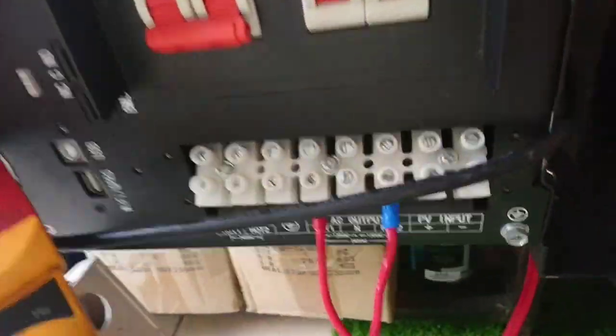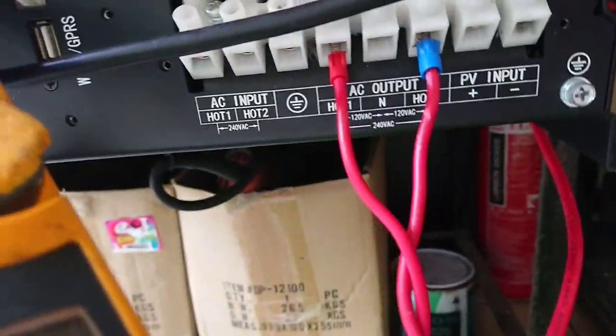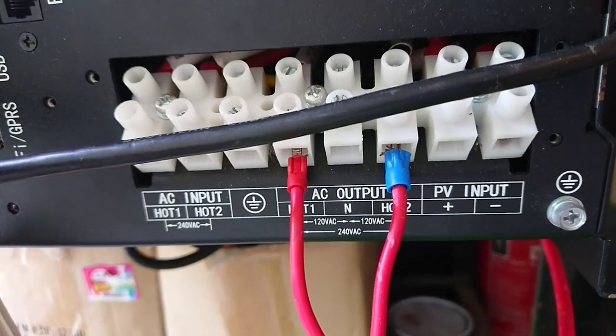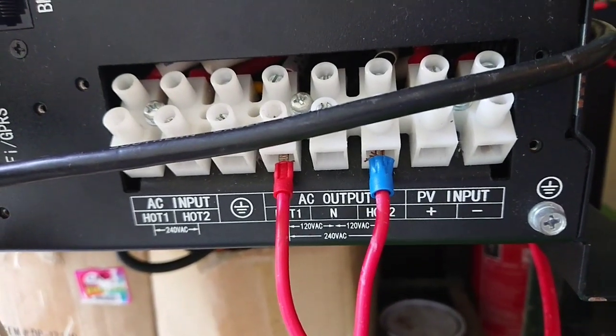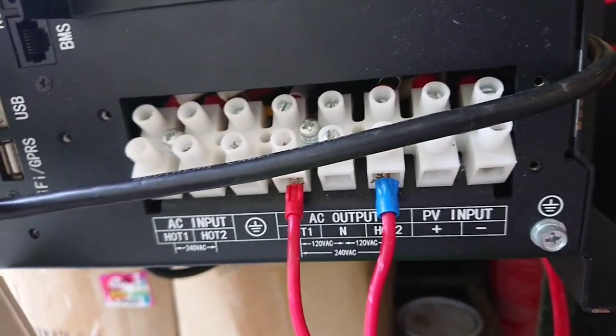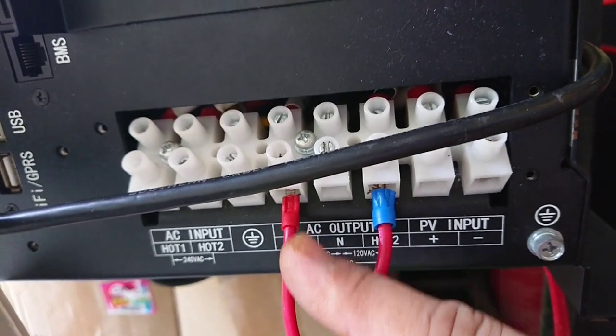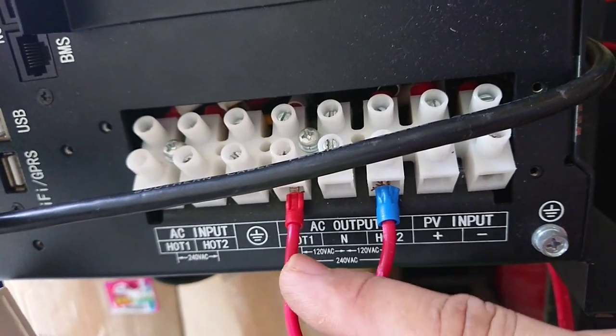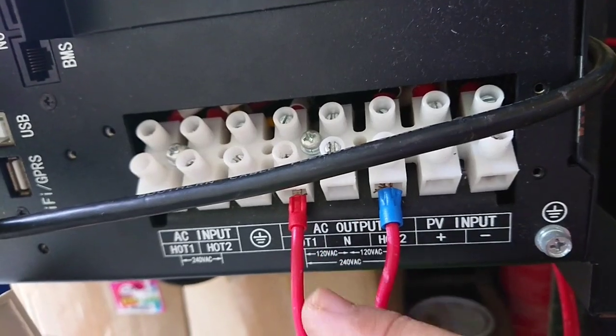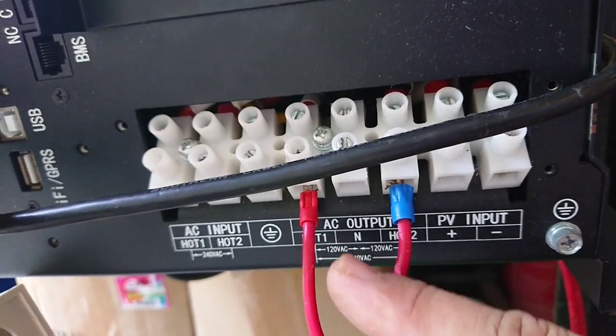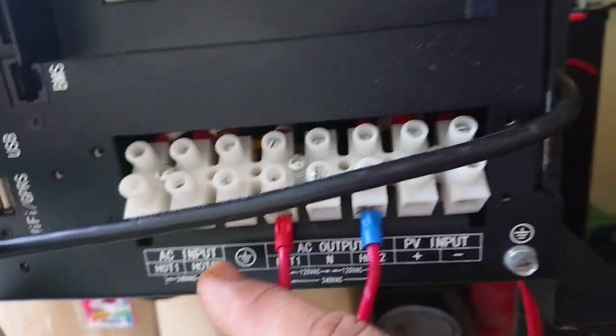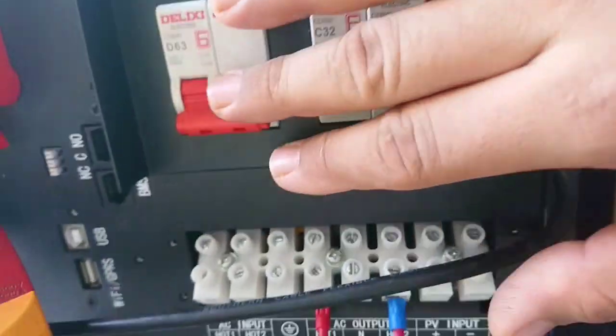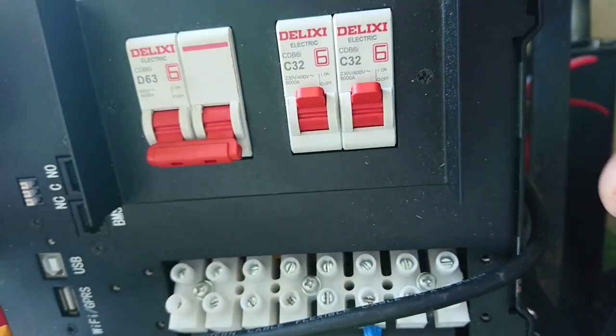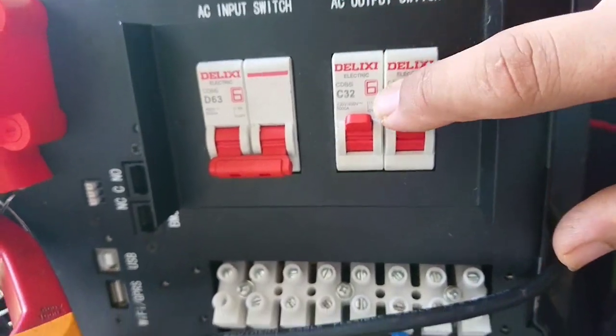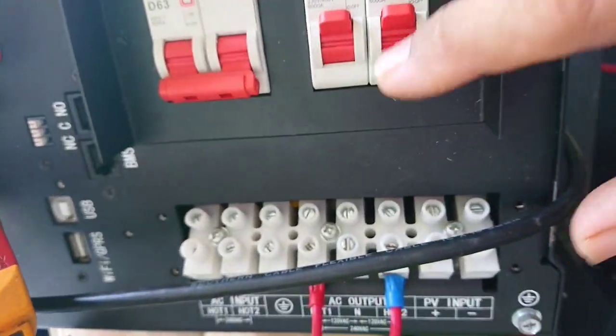The terminal has split phase, but our country, Malaysia, uses 240, so I just connect live and neutral here. So you got 230 or 240. This is the DC AC input for hybrid application, which I don't use, so that breaker I turn off. This is the AC output breaker, C32, so I turn that on.